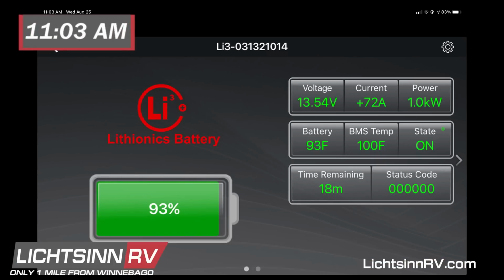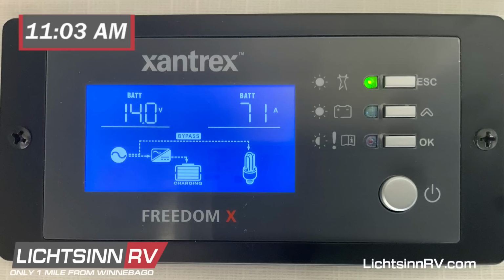And now you can see here at 11 a.m., 3 hours later, we're up to 93%, 13.54 volts. A battery temp of 93, and an internal battery management system or BMS temp of 100 degrees. And then also you can see it's actually dropped and it's getting closer to float mode now. It's actually only applying 71 amps.